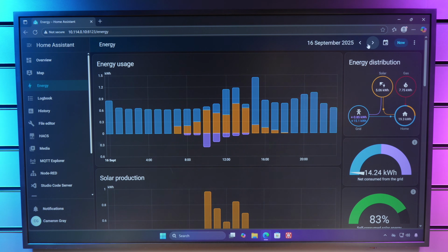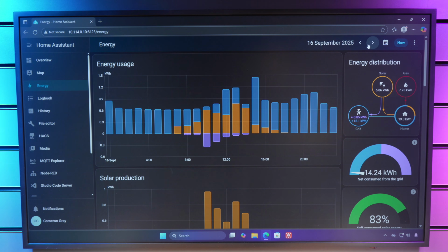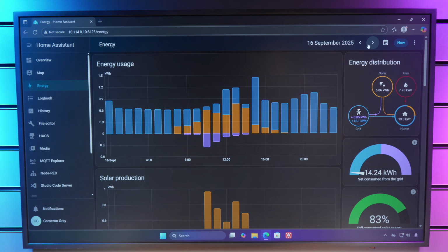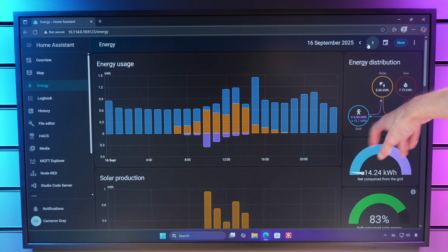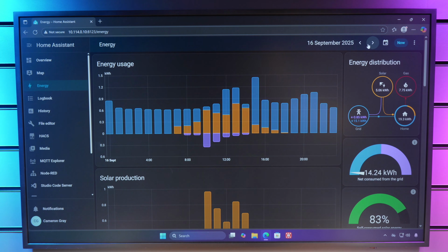In terms of the accuracy, here we have the energy dashboard for the first full day that I had it installed with those CTs doubled up. And as we can see, it's reporting that I imported 15.1 kilowatt hours from the grid and exported 0.85 kilowatt hours. Taking a look at the same day on my energy provider's app, it's tracked me as pulling 15.4 kilowatt hours from the grid and exporting 0.9 kilowatt hours. So very, very close. We're 0.3 kilowatt hours out on the import, and the export is essentially a rounding error because their app only shows one decimal point. So with that setup with the CTs doubled, the accuracy is perfect. I can't see any issue there at all.